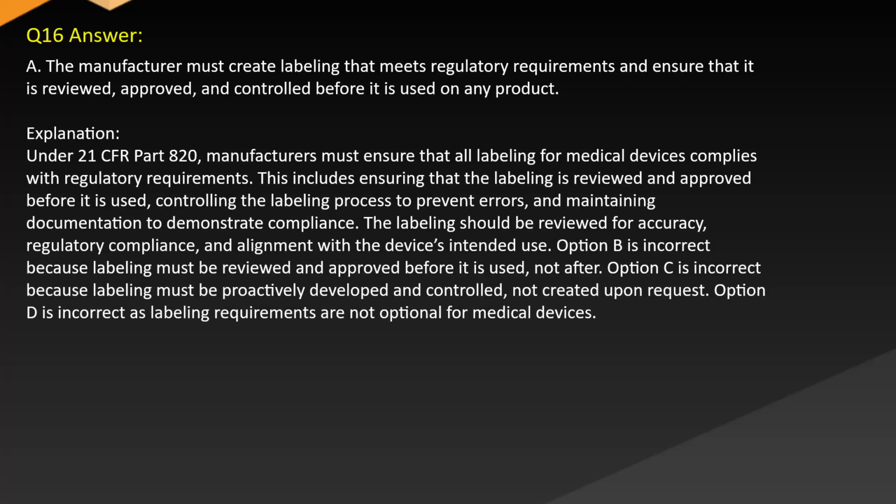Answer A. The manufacturer must create labeling that meets regulatory requirements and ensure that it is reviewed, approved, and controlled before it is used on any product. Explanation: under 21 CFR Part 820, manufacturers must ensure that all labeling for medical devices complies with regulatory requirements.